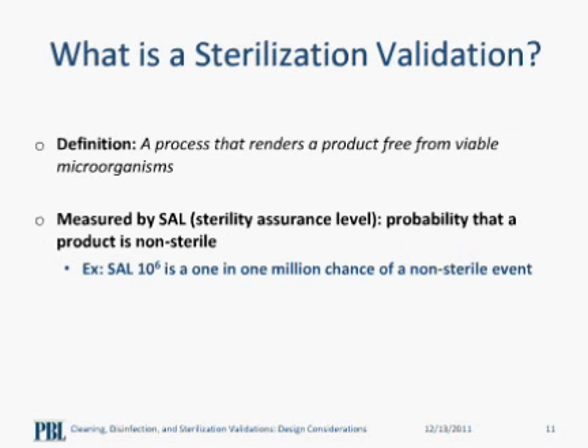For devices which are required to be sterile, sterilization is the only option after cleaning. Sterilization is a process that renders a product free from viable microorganisms and is measured by the sterility assurance level. This is the probability that a product is non-sterile. For example, an SAL of 10 to the minus 6 is a 1 in a million chance of a non-sterile event.